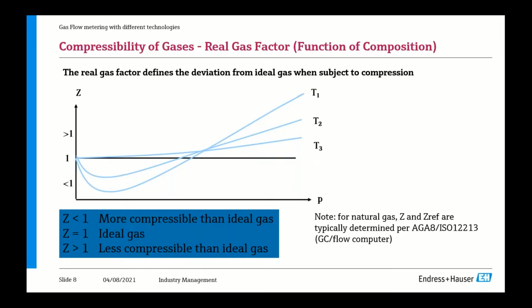Typically, for a gas, you will always strive to calibrate a gas meter, if you can, on a liquid, and not on a gas. Only if you have to, you will do so, because the best gas rigs that you find, they are in an uncertainty range of maybe 0.3%, and the best liquid rigs that you get are in the range of 0.015%, so a factor of 20 better. Talking about the Z factor, you see there are certain equations available, like the AGA8, ISO 12213, and those are typically in your flow computer or in your gas analyzer.